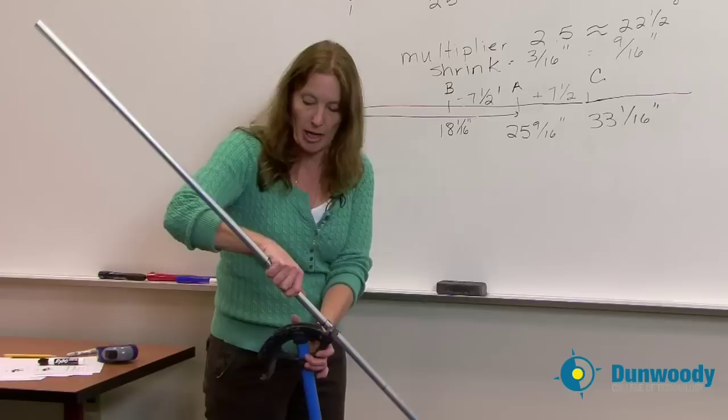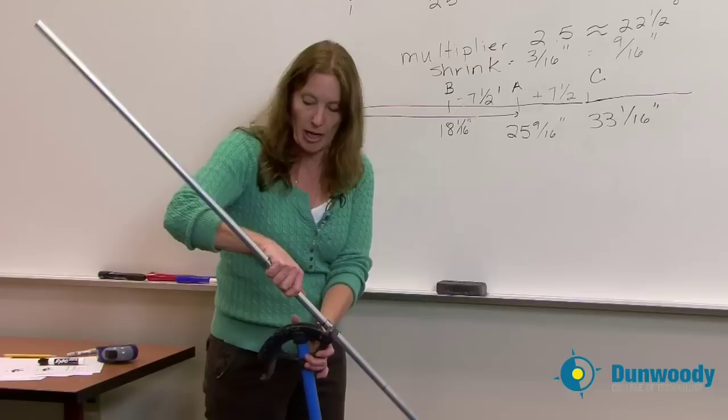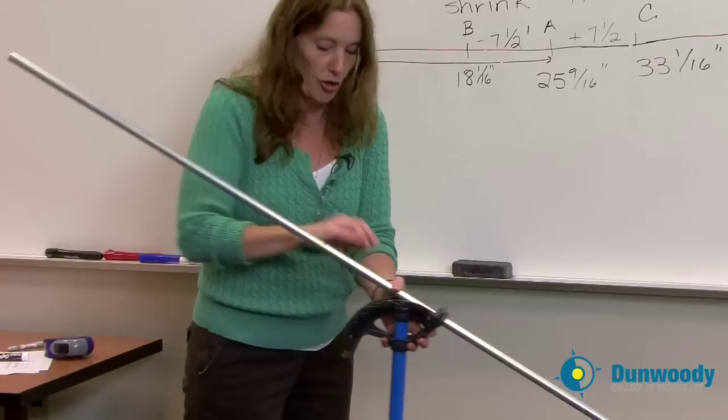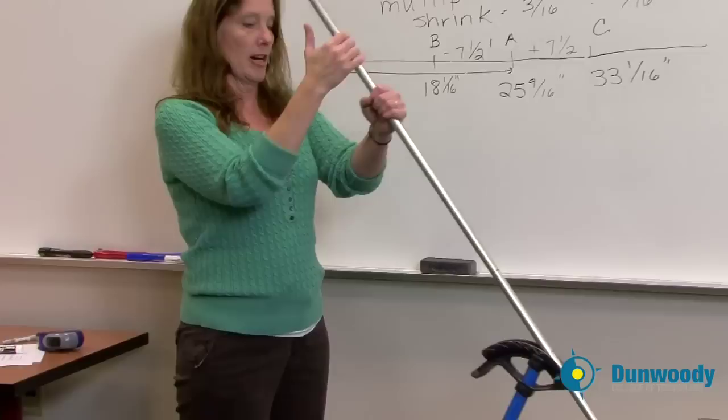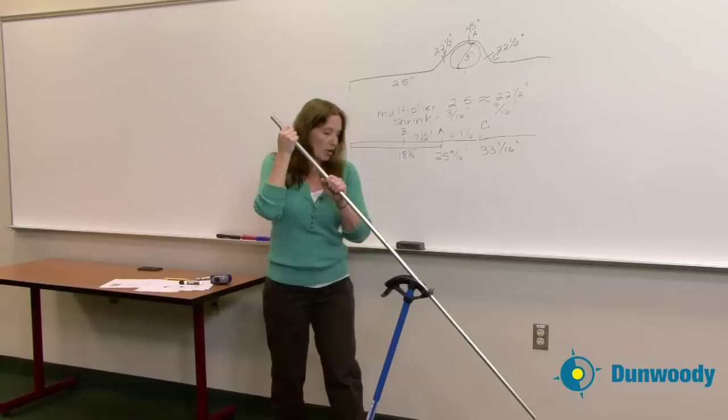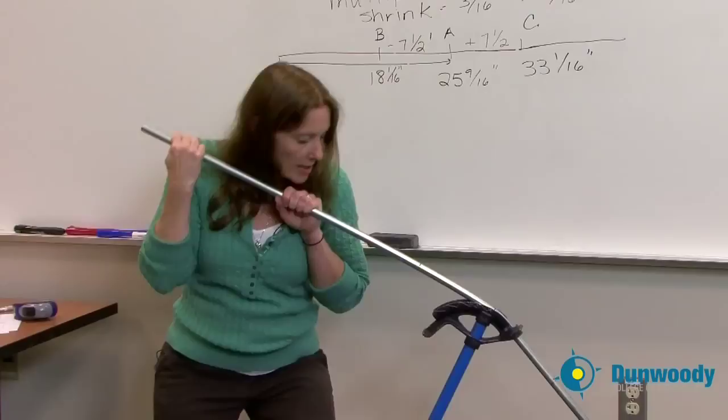I'm going to take and put the notch at that A mark. So I find my A mark which is my center mark and I'm going to match it up to the notch in my bender shoe. Once I have that marked, notice I am facing the direction that I measured from, and I'm going to put that bend in place. I'm going to take it down to a 45 degree bend.